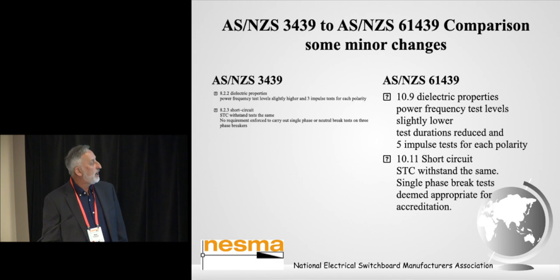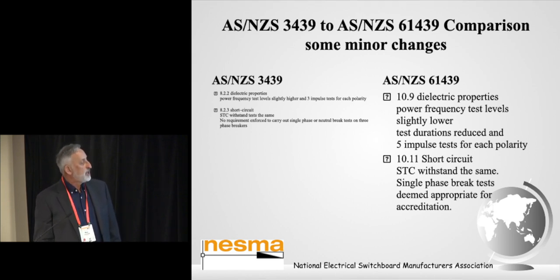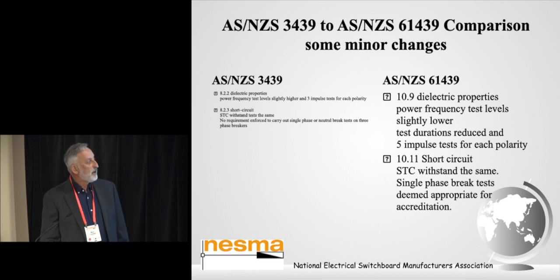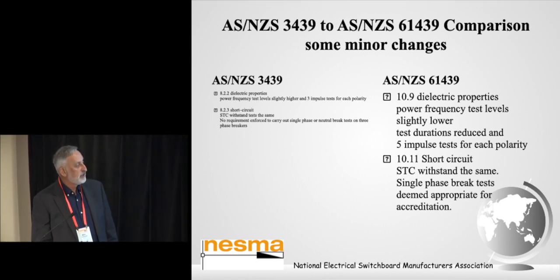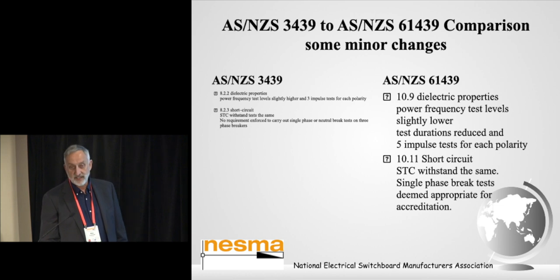We have some minor changes starting to appear. In the dielectric test of 3439, which is 8.2.2, the power frequency test levels were slightly higher, and we only had 3 impulse tests on each polarity to validate an impulse rating for the assembly. So clause 10.9 is the new clause for 61439. Here the power frequency test levels are slightly lower. Test durations were reduced, down to a 5-second test duration. But that said, the latest edition of Part 3 is taking it back to a minute anyway.